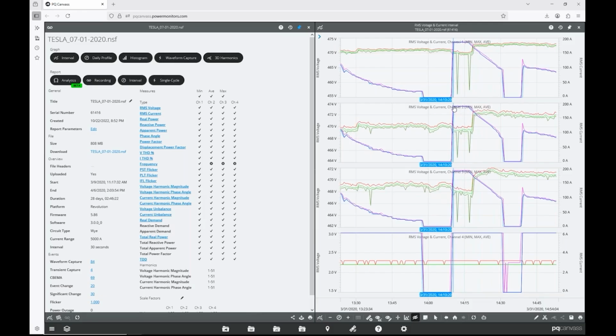So here, this flat portion of the current is at maximum charge, and we have some deep voltage sags during this time, and that really caused no effect on the current. So these chargers are fairly resistant to these sort of deep voltage sags, unlike, say, a motor or motor protection. And you can actually see, if you look closely, a little increase in current. They increase their current as the voltage drops to keep a constant power.